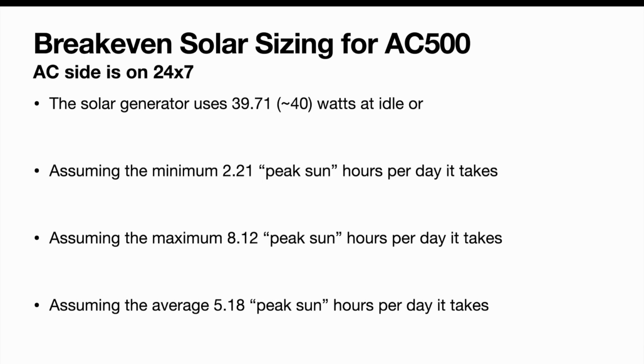What you do is take the solar generator's watts and multiply by the number of hours it's on to get watt hours. So 40 watts times 24 hours equals 960 watt hours just to keep the thing turned on. This is a 3 kilowatt hour battery, so we're using a third of it every day just to keep the inverter turned on.